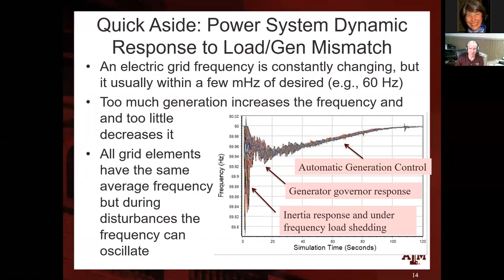When the frequency starts to come back, actually, as it's coming back, the generators have governors on them. These are automatic control devices that increase the mechanical power into the device to make up for the lost generation somewhere else. So within seconds, we get the governor response. That does not restore the frequency back to 60 hertz, but we have another control system known as automatic generation control that over the course of many seconds to minutes will restore the frequency back to 60 hertz. And on this project, because we were connecting the eastern and the western grids, we were modeling all of these different response mechanisms.